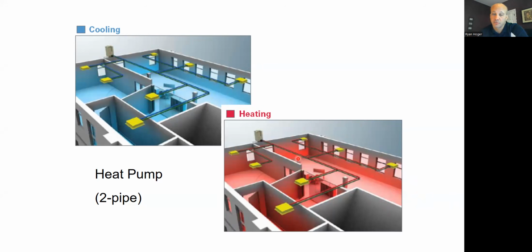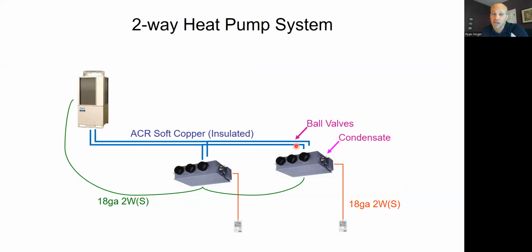Right? From an installation standpoint, you'll have copper lines running to all these indoor units. What happens on the majority of manufacturers is I'll leave the outdoor unit at a fairly large pipe size. And as I get further away, so I don't know what the size is, but let's just say, I'll make up numbers for right now. Let's just say this is a 1-inch line right here. And then I'll pull some BTUs off on this tapping to go to this first unit. And that means this is no longer a 1-inch line. Now this is a 7/8 inch line going over here, right? And as you get further away, it gets smaller and smaller.